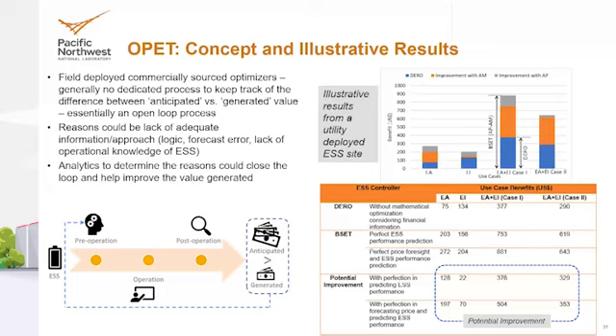One is a lack of understanding regarding the battery's performance, which we found to be quite significant. There are cases when the utility expects 90% round-trip efficiency when they're actually getting 68%, and they expect significant economic returns when they're actually losing money because of those losses.